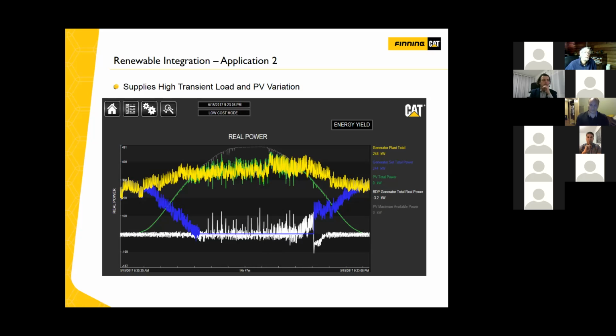Another important aspect of this grid: at the very top you can see a bit of the bell curve gets chopped off, that white bit, and that's PV curtailment. At that point the PV can actually generate more power than what's needed, meaning the load isn't calling for it and the batteries are fully charged. So the master microgrid controller dials back the PV power generation just so there's not excess power on the bus. Then at the end of the day, the batteries are fully discharged, and as the sun goes down, the diesel generators kick online, charge up the batteries, and make up the difference in the power generation curve. That's a clear snapshot of a typical day in a hybrid system.